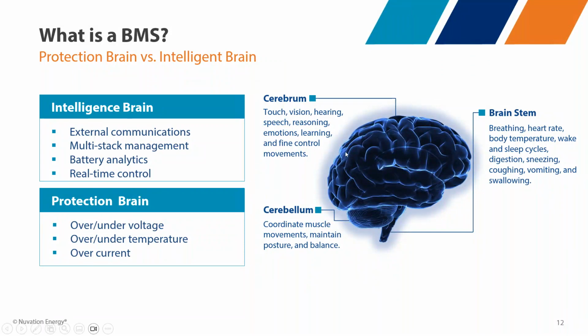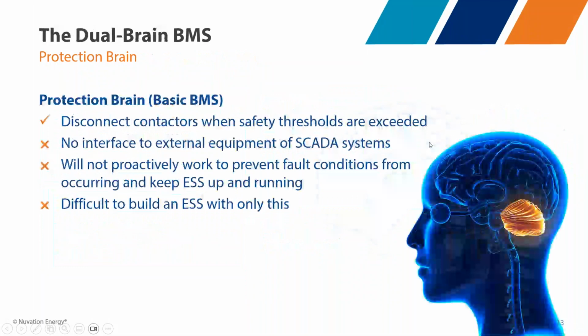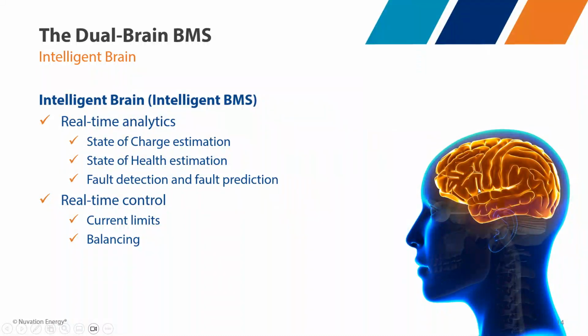I have to do a comparison to a brain. The protection brain is like your lizard brain, your cerebellum, your brainstem, whereas the larger brain does a whole lot more. So your protection brain is that very basic BMS that simply disconnects contactors when thresholds are exceeded, but you don't have all this other stuff - no external communication, no fault prediction. It's pretty hard to build a modern energy storage system with a really basic BMS. An intelligent BMS is the much larger part of the brain, and this is where we add all the real-time analytics, state of charge, state of health, fault detection, fault prediction, and all the data analytics that goes with that.